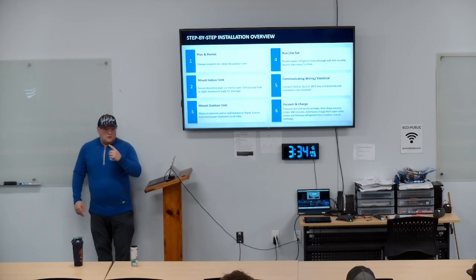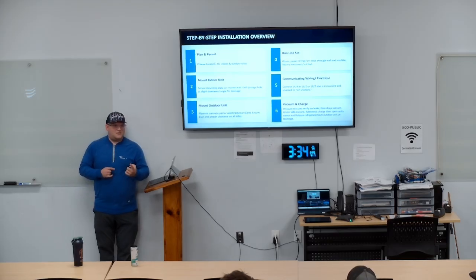So the new question is, I've been telling people, I might get corrected for this soon because I'm going to bring it up to Dan, but they've started doing, if there's communication that runs from inside to outside, there's also the power feeds from the outdoor to the indoor. I've started to tell people, if you see that, run the 14-4 and the communication wire. So we have them both. Because still electricians are like, oh, I didn't have that on my scope. We've already got the wires there now. We ain't got to worry about pulling back through. It's becoming more and more common.